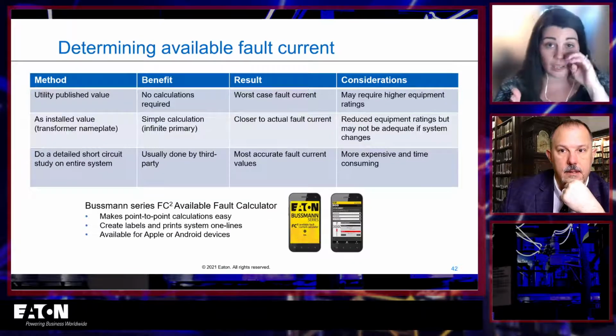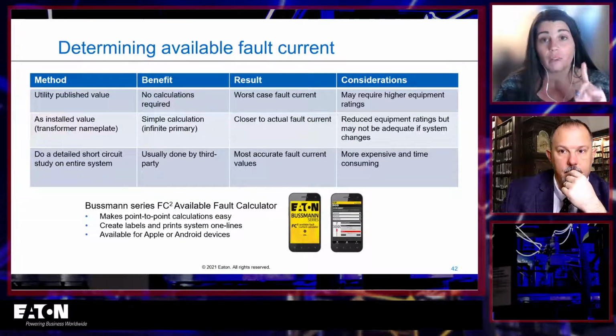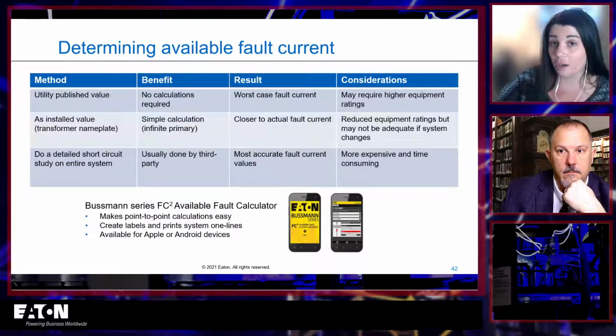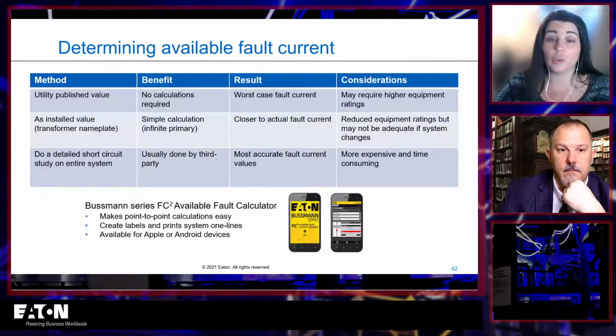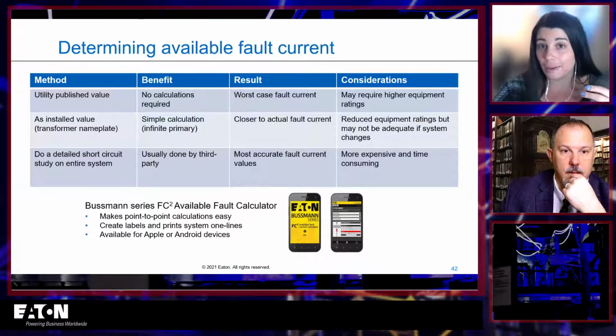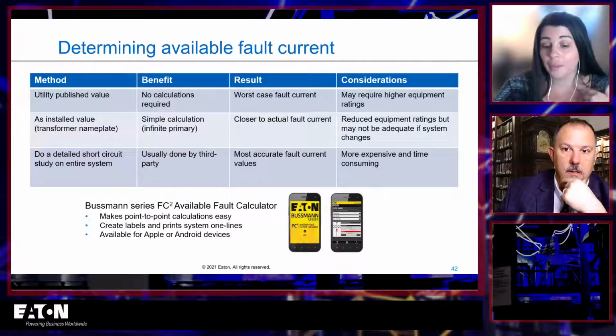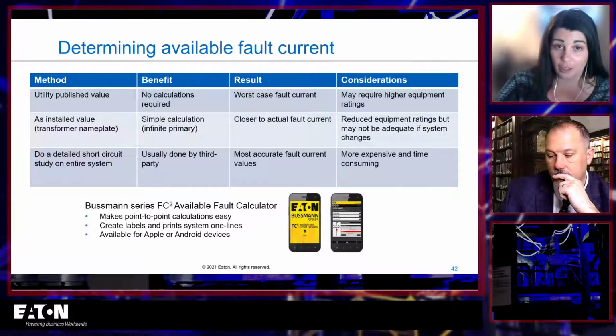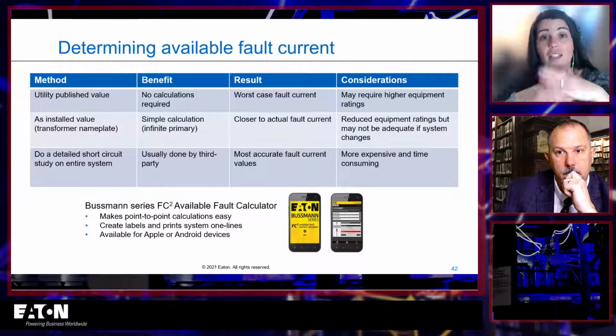If you can't get that information from the utility, but you have information about the transformer that's installed coming in, you can put in basically the nameplate info from that transformer, and it'll tell you an available fault current. And then again, you can continue to build your system.